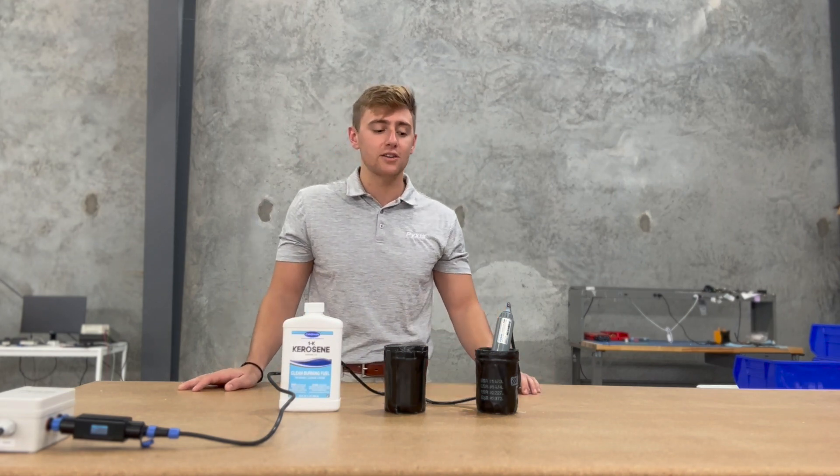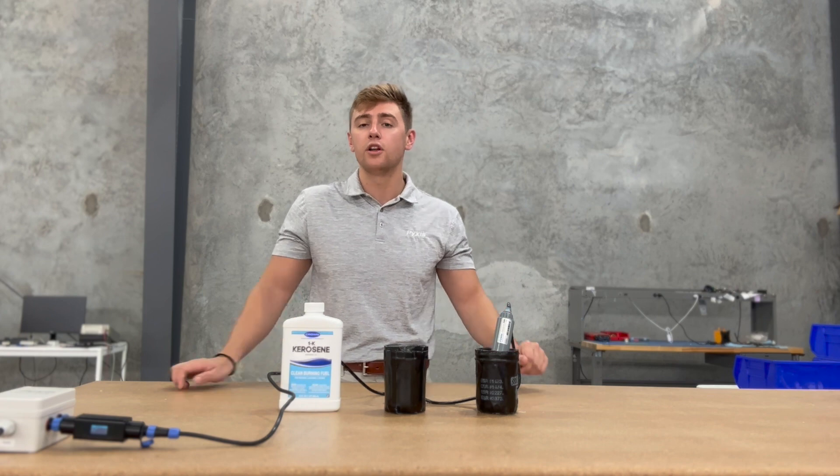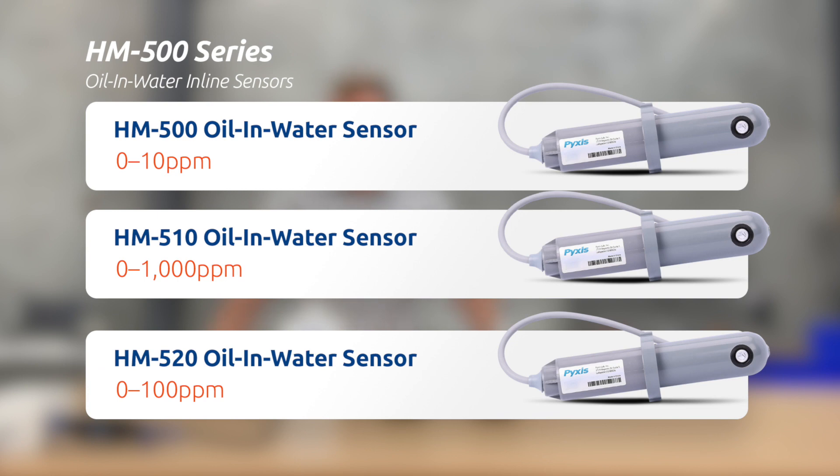So the HM series consists of the HM500 which measures at a range of 0 to 10 ppm and we have the HM510 which measures at a range of 0 to 1000 ppm and the HM520 is 0 to 100 ppm all measuring for oil in water concentration.